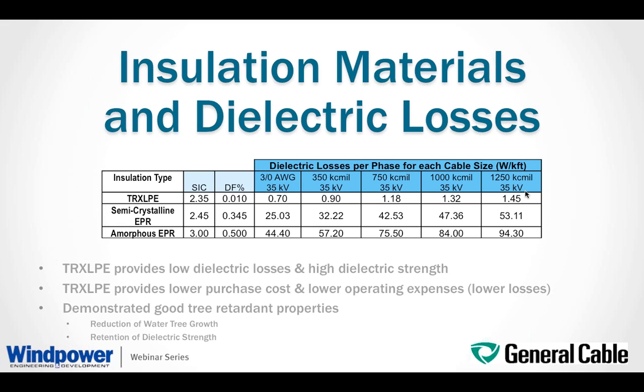So here, going to the insulation materials. In North America, there are primarily two main types of insulation material used for medium voltage power cable applications: the tree retardant cross-linked polyethylene and then EPR, as Brandon was pointing out. EPR are typically formulated and compounded by the cable manufacturers, so there's a number of different EPR materials being used.